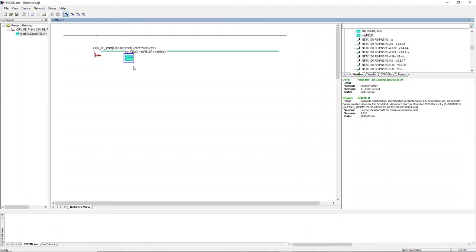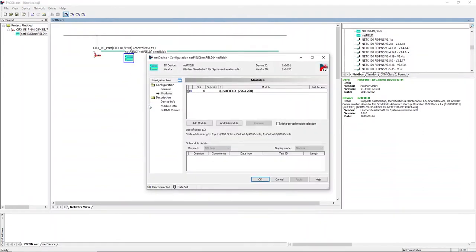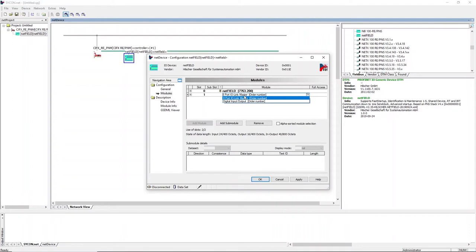Right-click the device and select configuration to change the current default configuration delivered by the GSDML file. Select the module configuration and add a new module. Since this is an 8-port IO-Link master gateway, select the fitting module.